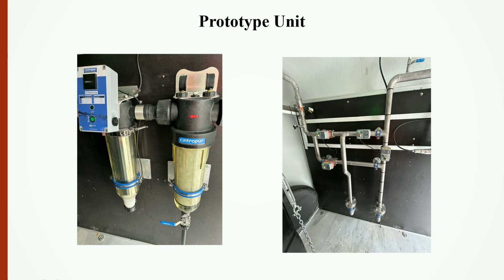On the other side of that, we have the feed from the pump, which will come in, go down into the loop, return back from the loop, and return back to the degassing tanks. And then those 4 valves will alternate, and we'll have the flow coming in this way. It will divert through that way, go out through the reverse flow, come back, and then go back to the degassing tank itself. So that tests the flow rate in the 2 directions which we require.